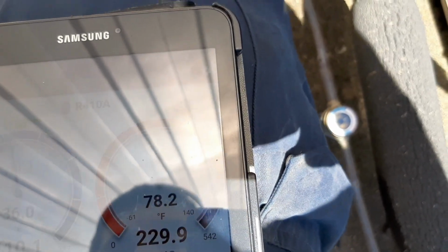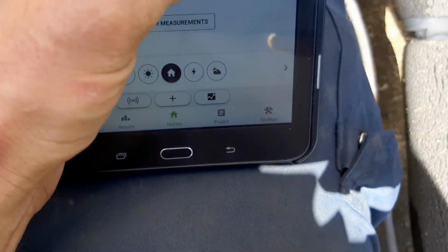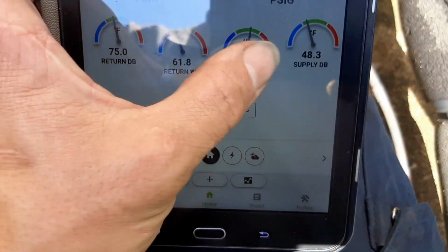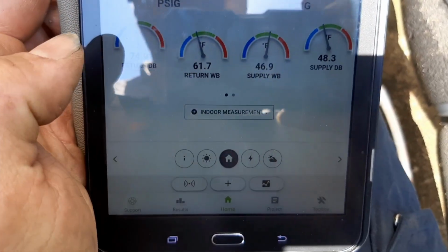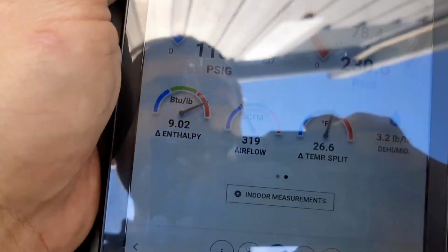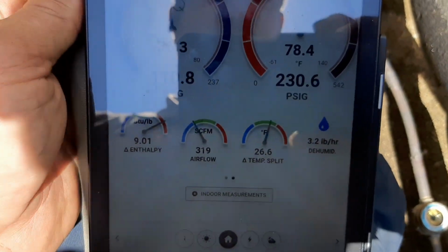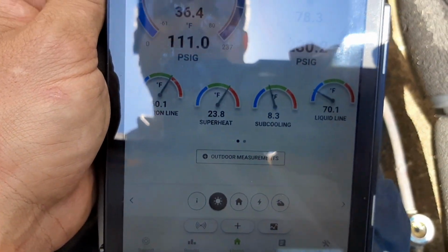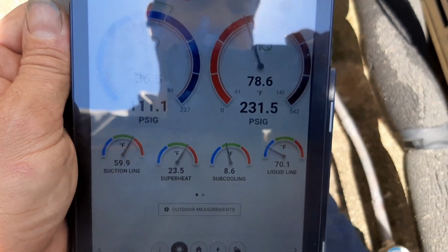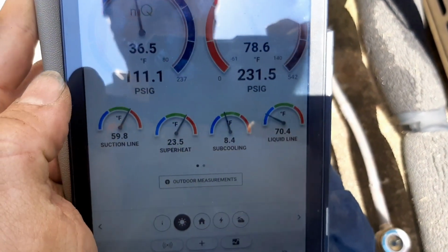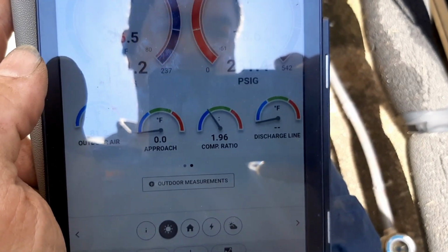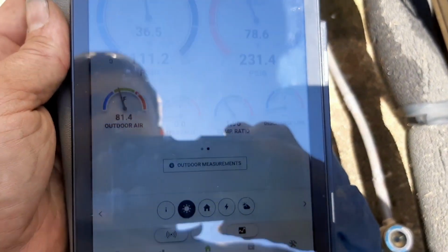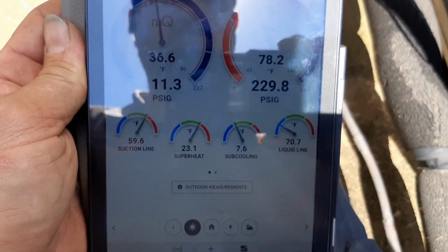It's cooling. I'm not in the best place for that supply temperature reading. So I am still reading a really high temp drop. But we got airflow issues we know of. It's sticking about that 26 mark. So we'll let the coil dry out real good. It's gonna at least cool this way. Compression ratio is alright. As long as the superheat gets in range, we'll just write it up as such and let them know what they got. But it's improving as it runs.